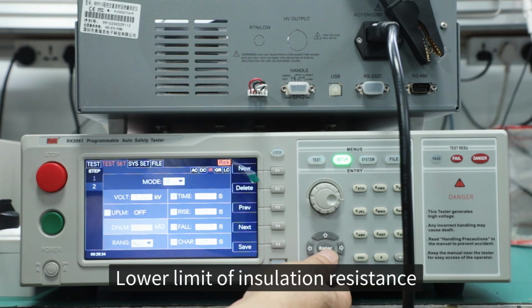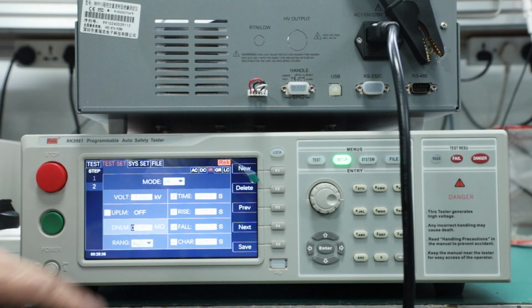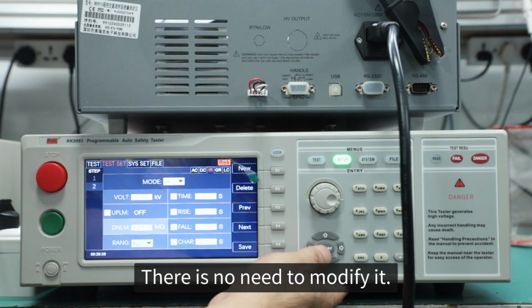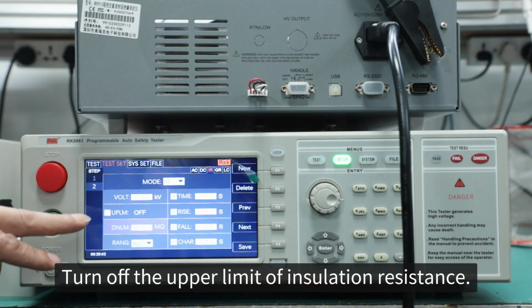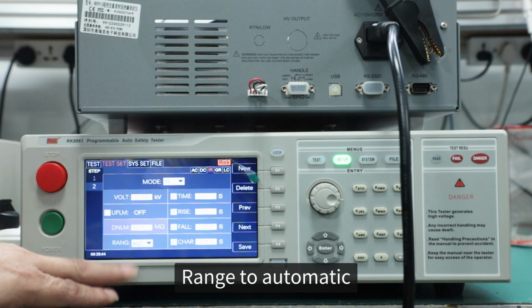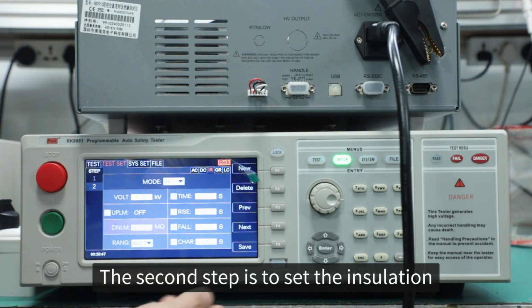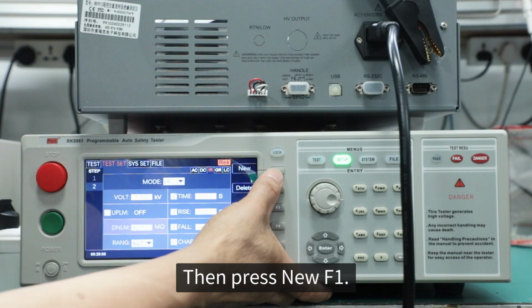Lower limit of insulation resistance, the lower bound is 10 megohm. There is no need to modify it. Turn off the upper limit of insulation resistance, range to automatic. The second step is to set the insulation. Then press New F1, New.